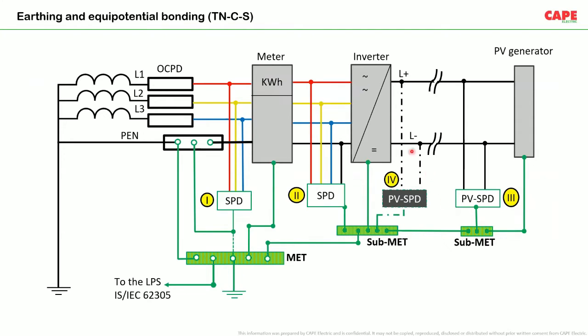People will ask, then what do we do with positive and negative? Shall we earth it or not? Never. You are never allowed to earth the positive or negative. Of course, that particular earthing is made inside the inverter, and that is the decision of the inverter manufacturer. If the inverter manufacturer recommends a positive or negative earthing, it is written in their manual. You have to read the manual and decide whether the DC side is to be earthed or not. Otherwise, neither DC positive nor negative shall be earthed. It has to be a double insulated installation, which we will discuss later.